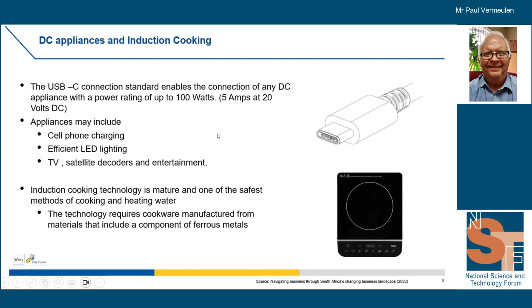DC appliances and induction cooking. So the USB-C connection, the one you use on your cell phone these days, if it looks like that little round one and not the old D-type one, that is capable of delivering up to 100 watts of power, 5 amps at 20 volts DC. So within a residential setting, for example, this can be used to connect various appliances up to an energy storage system. And those appliances can include cell phone charging, efficient LED lighting, TV satellite decoders, and entertainment systems. Induction cooking technology is also mature and one of the safest methods of cooking and heating water. However, that technology does require cookware that's manufactured from materials that have a component of ferrous metals in them, but they're quite readily available already.